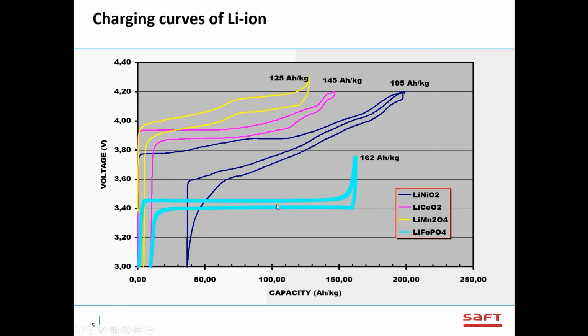Each of those chemistries have different voltage curves, different voltage characteristics from full state of charge to empty. So the light blue one, the very flat one at the bottom, is the iron phosphate battery. And I'm going to focus on iron phosphate because that's what we use for Flexion. You can see it has a lower voltage per cell, so around 3.3 volts nominal, where the other ones we consider 3.8 volt nominal. So with lithium iron phosphate, you get a lower energy density, but it has some benefits, mostly in safety that we're going to talk about, compared to the metal oxides.